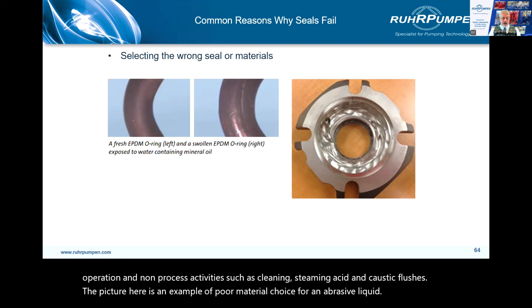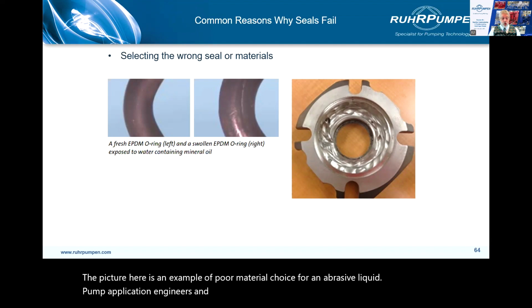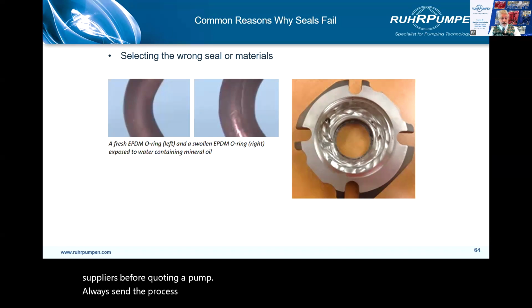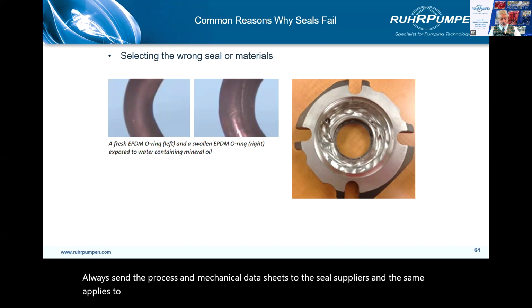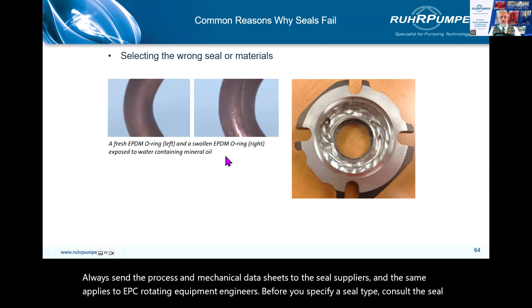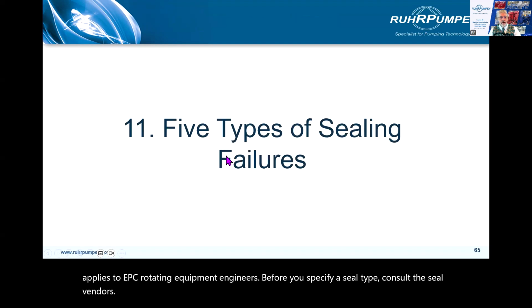Pump application engineers and salesmen should always consult the mechanical seal suppliers before quoting a pump. Always send the process and mechanical data sheets to the seal suppliers. And the same applies to EPC rotating equipment engineers. Before you specify a seal type, consult the seal vendors. Five types of sealing failures.